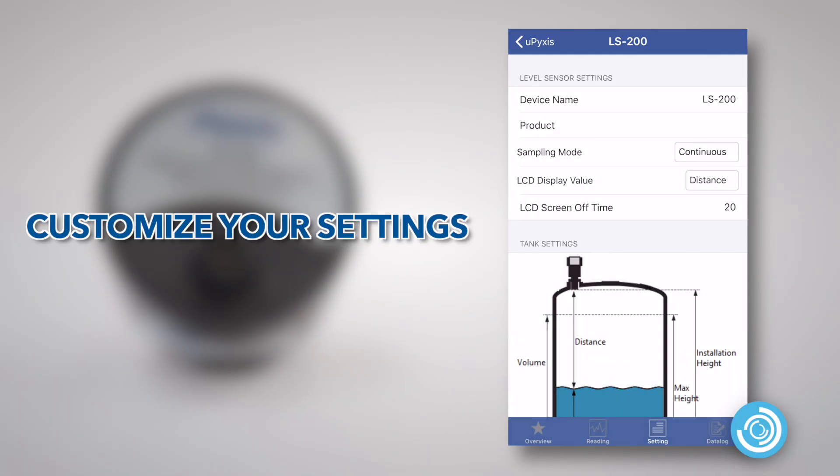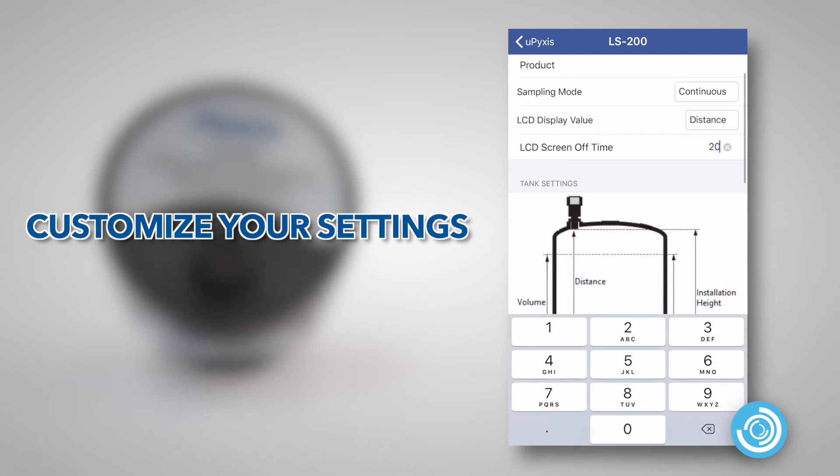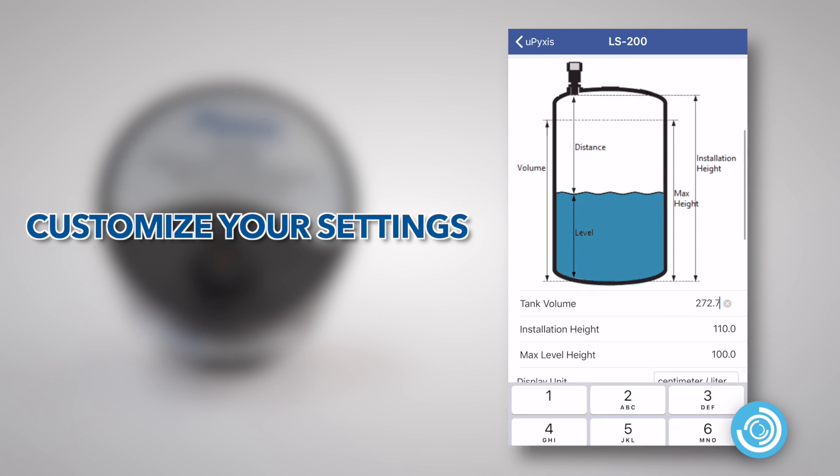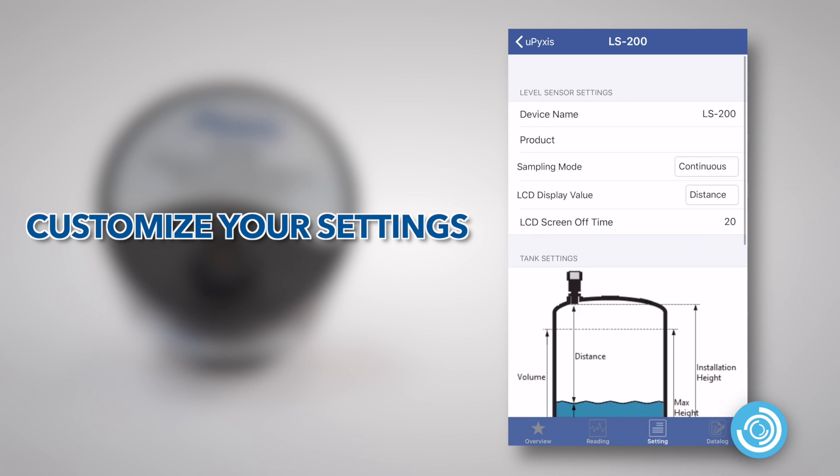When connected to the uPyxis app, users may program device name, product name, sampling frequency, units of display tank volume, and tank height. Once entered, this data will be stored in the LS200 device and sets the output scale of the unit for its receiving controller.